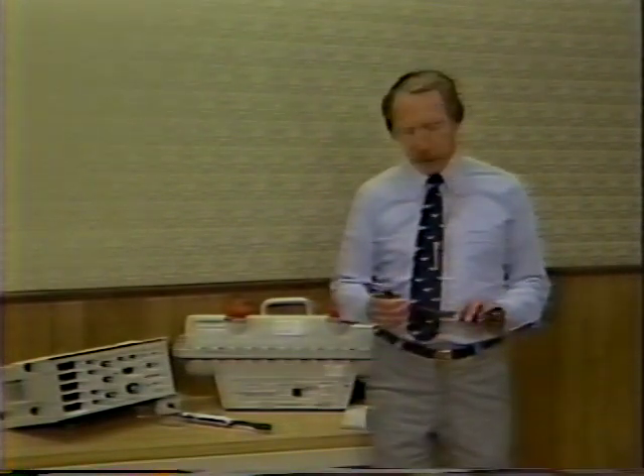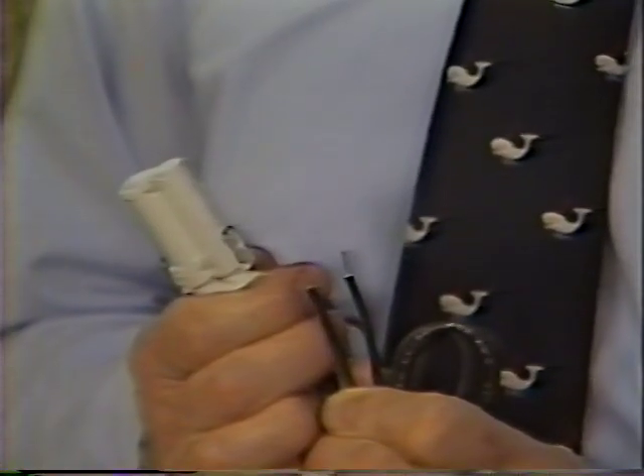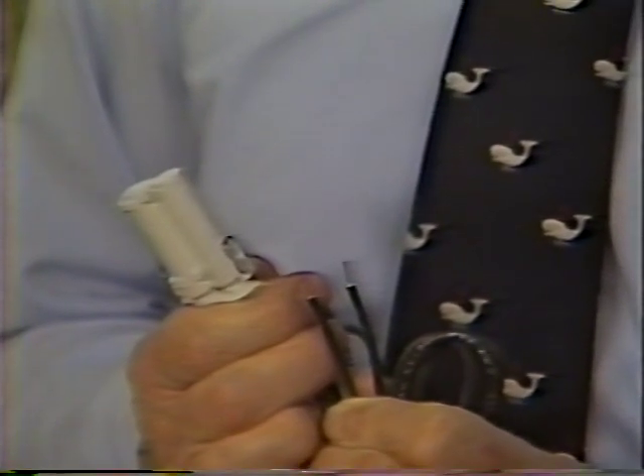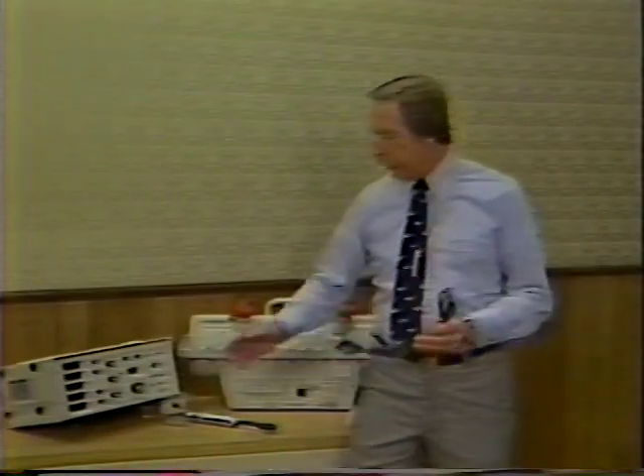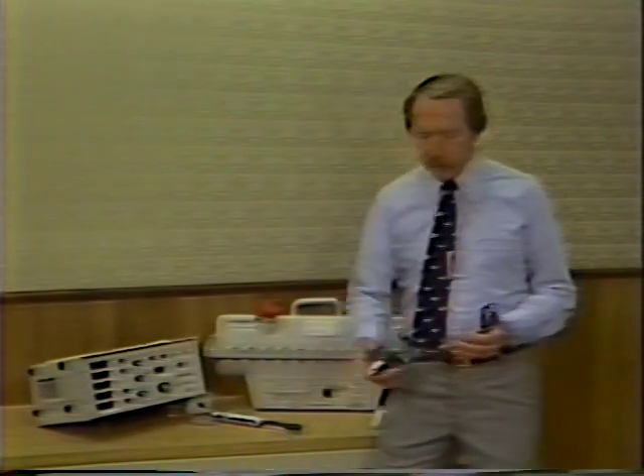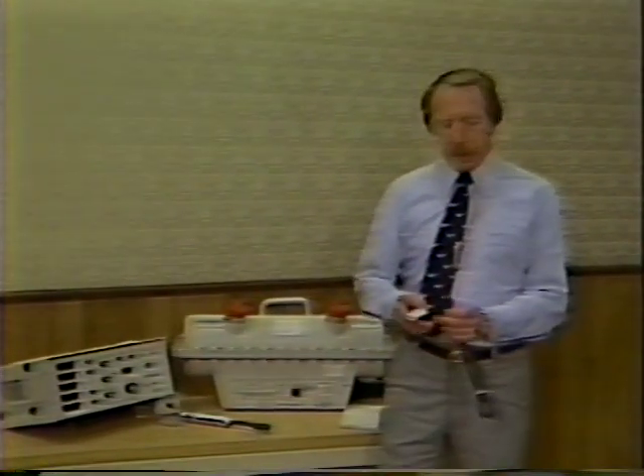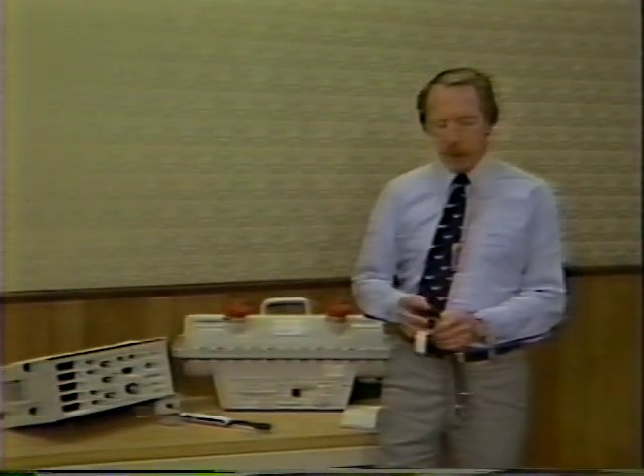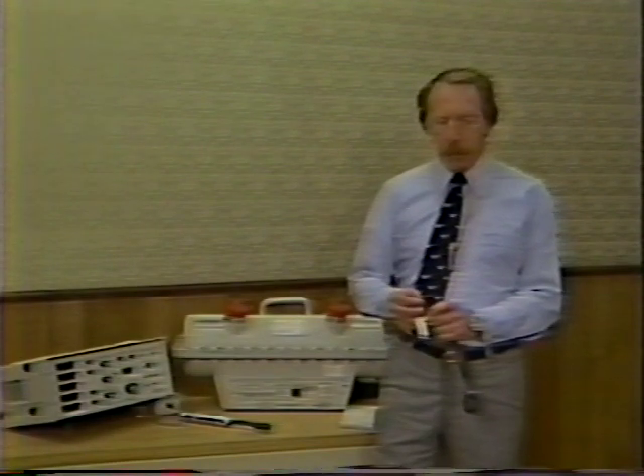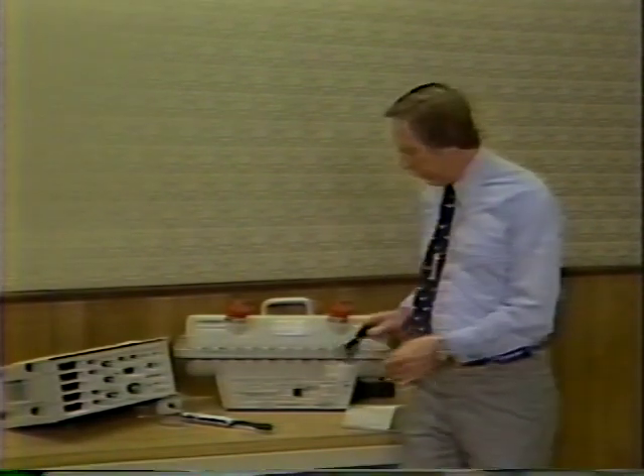We also provide with the Dynalyzer a 20-foot jumper cable that will allow you to pick up input line voltage to the generator. This connector connects into the rear of the Dynalyzer. The other ends are not terminated to allow you to terminate them in a manner that's most convenient for you for picking up the input voltage to the generator.